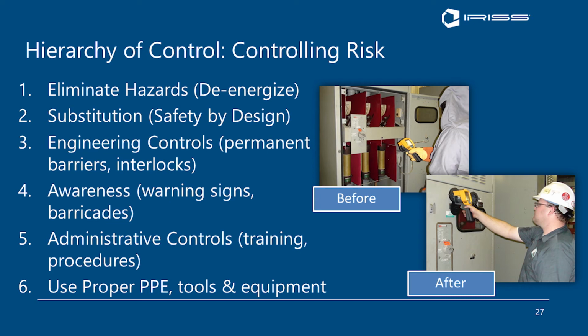Now, there are some condition-based tasks that I can't do de-energized. Remember the light bulbs, right? I can't do infrared de-energized, I can't do ultrasound de-energized, I can't do motor current. Well, there is one type of motor current testing I can do de-energized, but I can't do the energized type of testing, obviously. So then and only then do you move to number 2, substitution, also called safety by design.